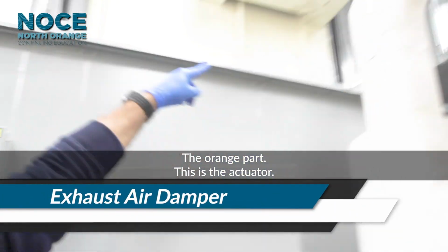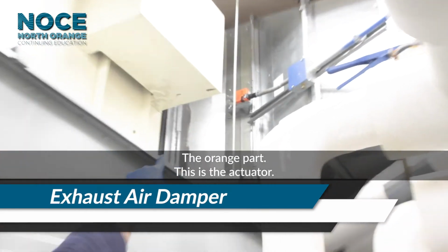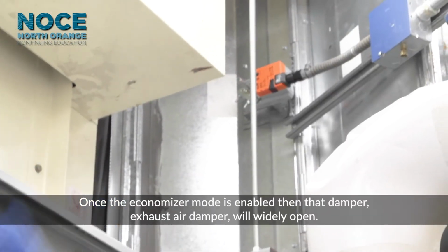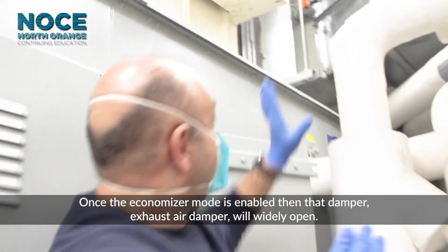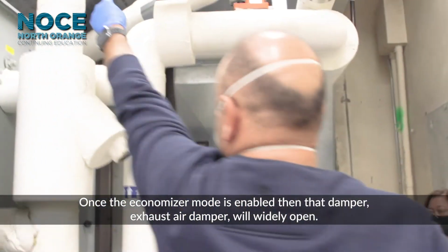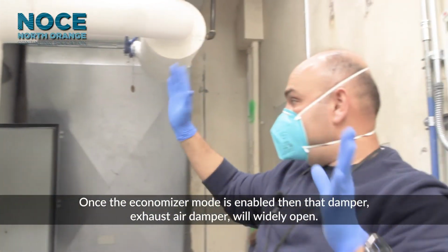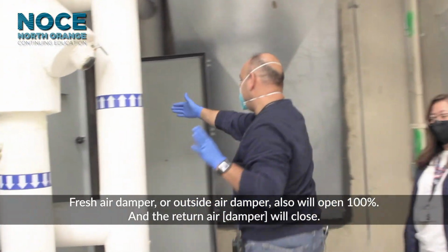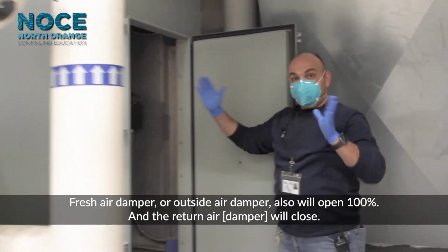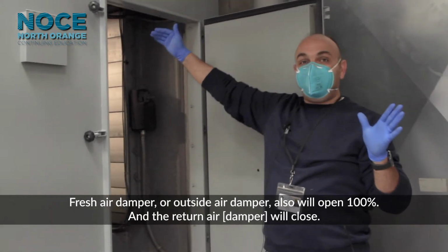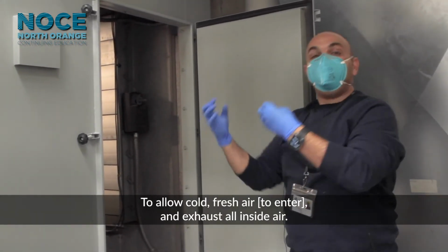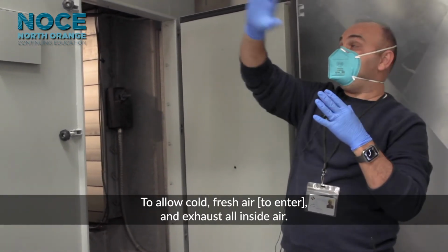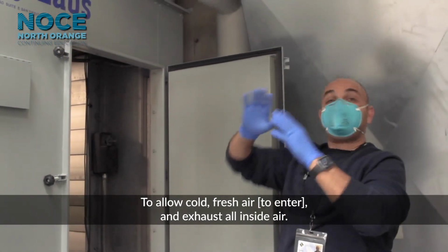Can you see the orange part? This is the actuator. So once the economizer mode is enabled, then that exhaust air damper is going to widely open. The fresh air damper or outside air damper will also open 100%, and they close the return air to allow to get fresh, cold, fresh air and exhaust all the inside air.